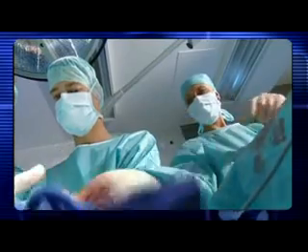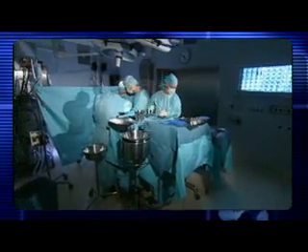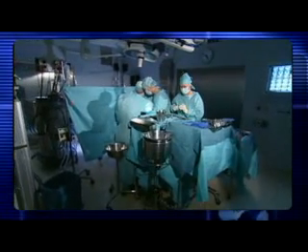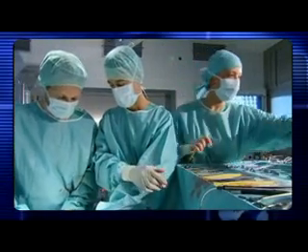We clearly have to make sure that we can read the chip safely and reliably. Secondly, we have to assure that the antennas and the whole infrastructure harmonize with the equipment installed in the operating room — making sure there won't be interference. And thirdly, nowadays the abdominal towels are being reused, meaning they are washed and sterilized. Accordingly, our chips have to withstand this process.